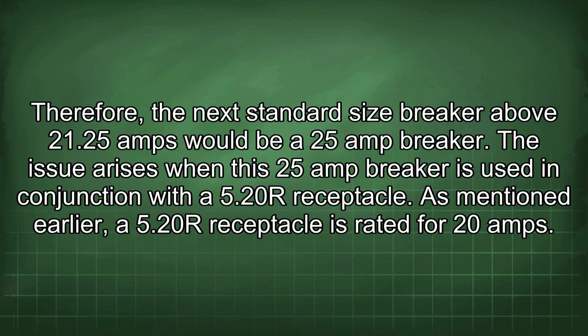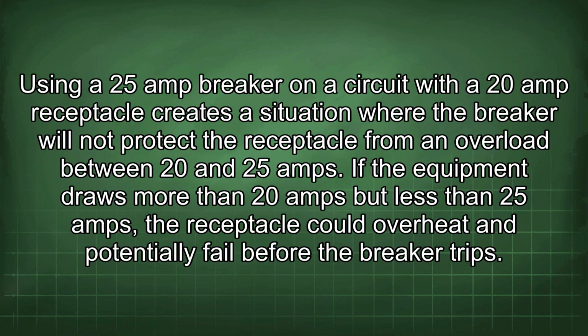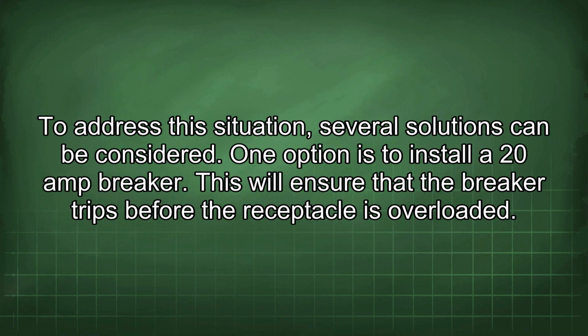The issue arises when this 25 amp breaker is used in conjunction with a 5.20R receptacle. As mentioned earlier, a 5.20R receptacle is rated for 20 amps. Using a 25 amp breaker on a circuit with a 20 amp receptacle creates a situation where the breaker will not protect the receptacle from an overload between 20 and 25 amps. If the equipment draws more than 20 amps but less than 25 amps, the receptacle could overheat and potentially fail before the breaker trips. To address this situation, several solutions can be considered.